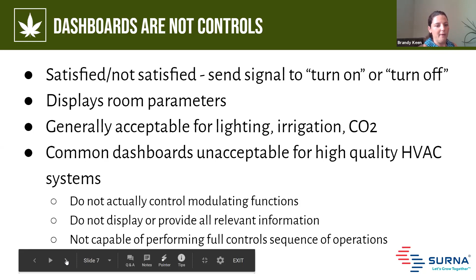So the manufacturers of those HVAC systems will often provide you with those controls directly. Sometimes you might want them to talk to a front-end user interface that also has irrigation, lighting, and everything else on it. That's possible, but the person providing that front-end interface needs to know what they're getting into—they'll often say 'yeah, we can talk to any HVAC system,' when the HVAC system wants them to pick up 1,000 points and they're only capable of picking up 10. That's important to understand about the skeleton of control systems, so everyone's on the same page when discussing this with possible providers.